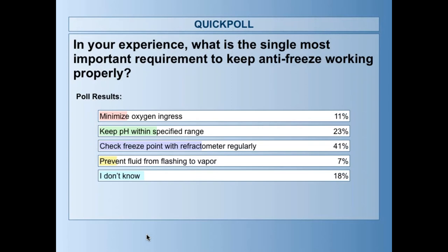A lot of the chemicals that the water treatment plant puts in there, like the phosphates and stuff for turbidity and other things they're treating the water for, will cause the glycols to gel, like Jeff Person said. So you do want to check the water you're going to blend the glycol with, unless you're buying pre-blended glycol that uses good water. The water you're mixing with can, from day one, compromise that glycol, break down the inhibitors, and actually start causing it to gel right out of the gate.